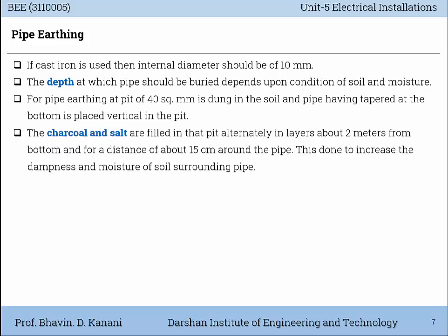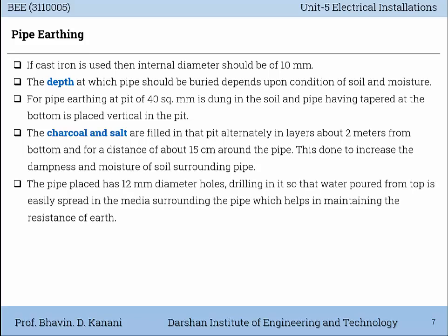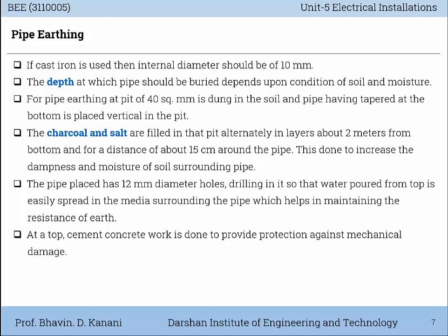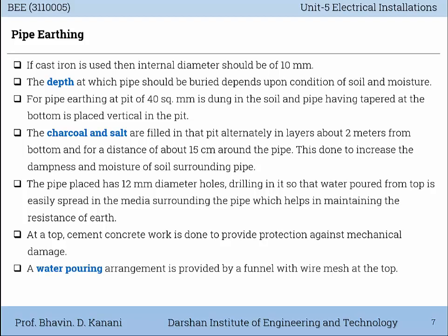The charcoal and salt are filled in that pit alternately in layers about 2m from the bottom and for a distance of about 15cm around the pipe. This is done to increase the dampness and moisture of the soil surrounding the pipe. The pipe placed has 12mm diameter holes drilled in it so that water poured from the top is easily spread in the media surrounding the pipe, which helps in maintaining the resistance of Earth. At the top, cement concrete work is done to provide protection against mechanical damage. A water-pouring arrangement is provided by a funnel with wire mesh at the top.